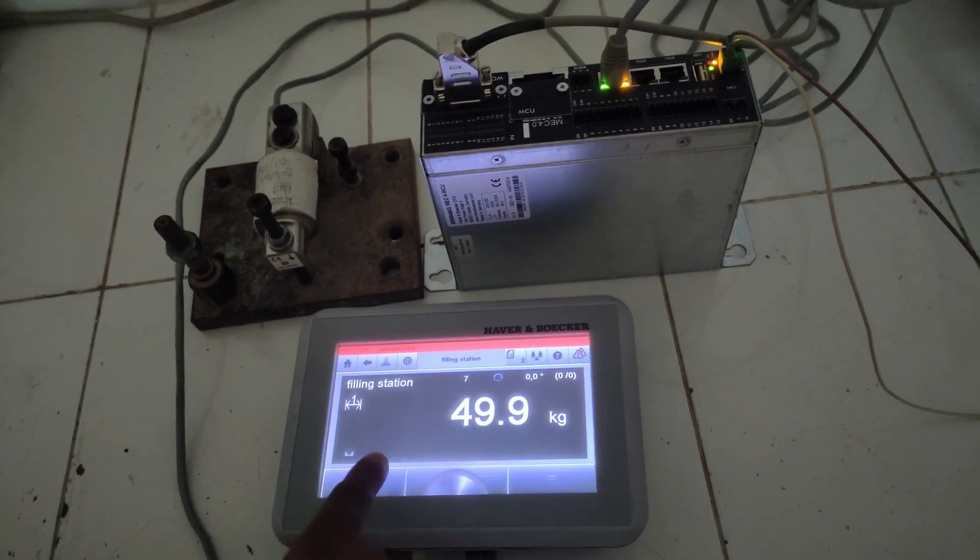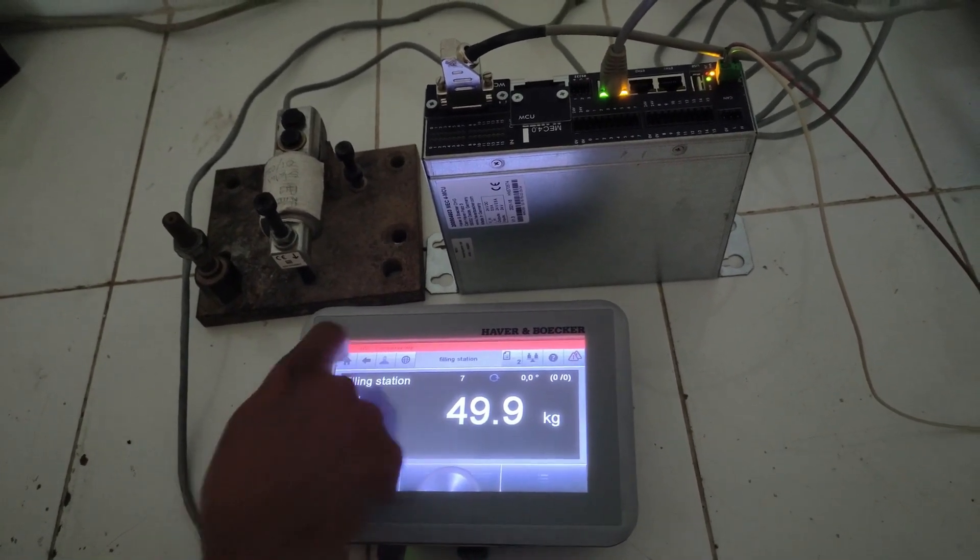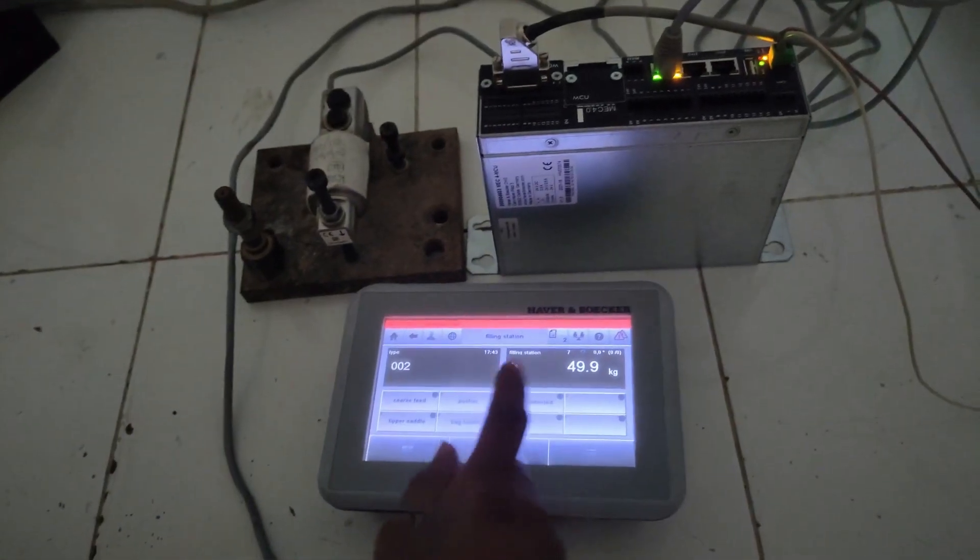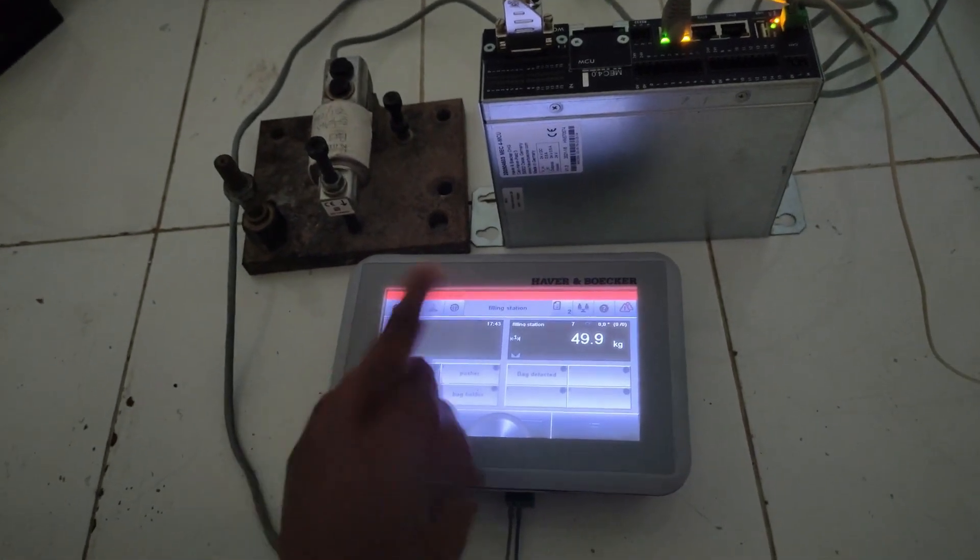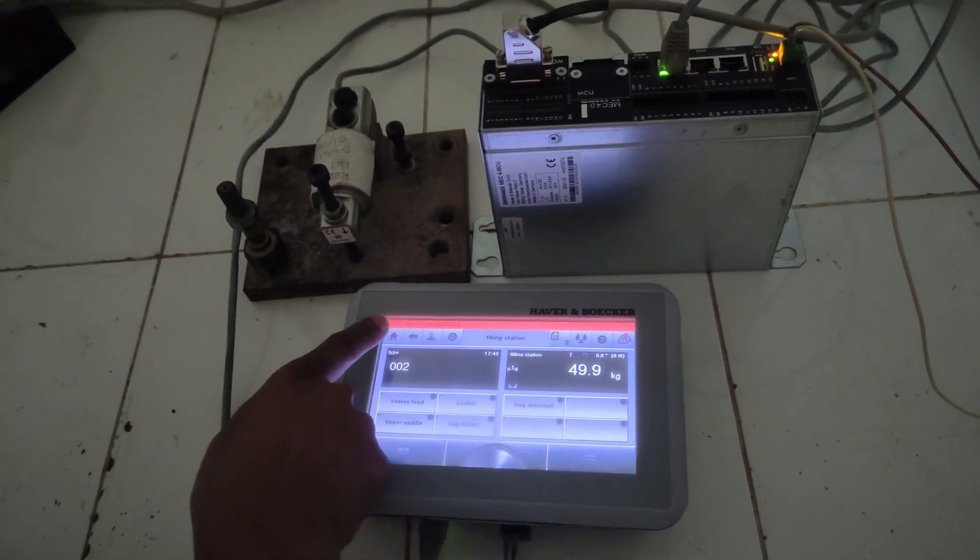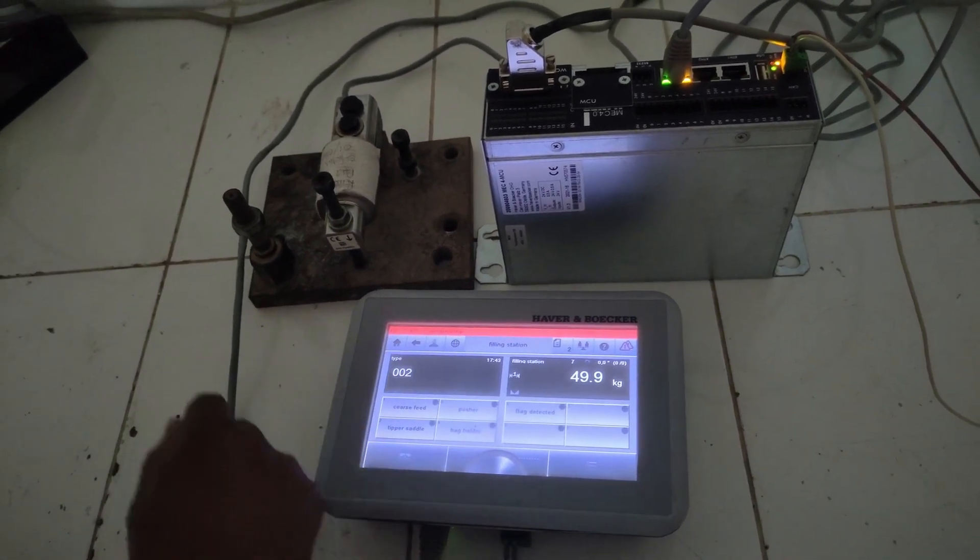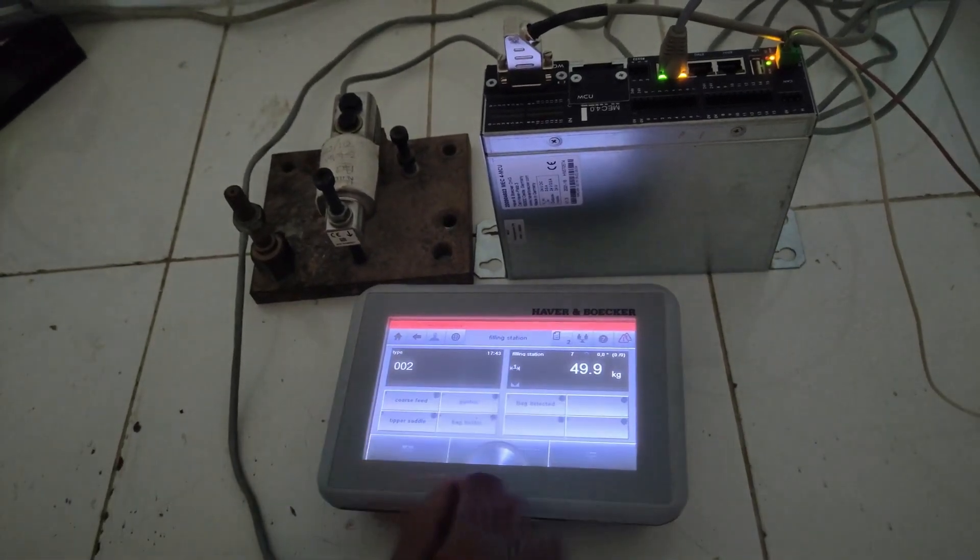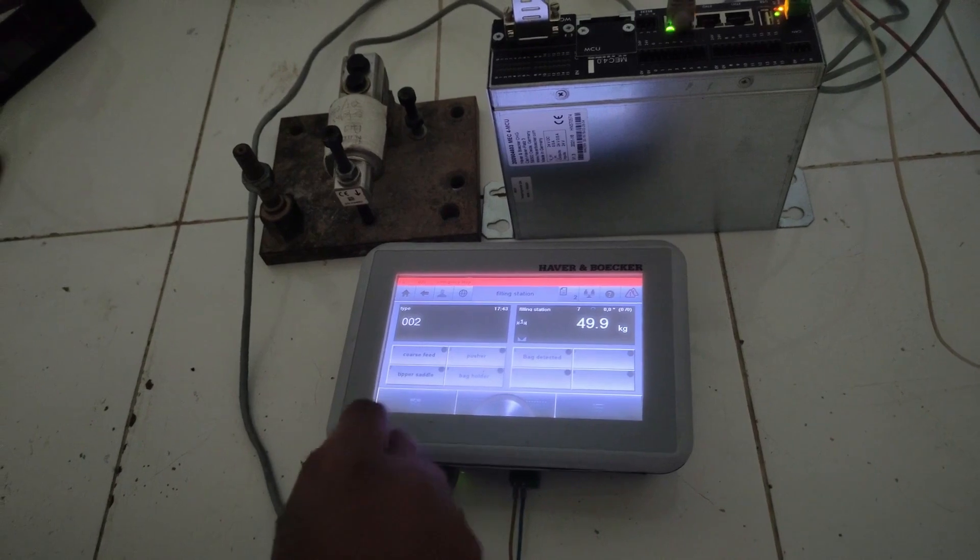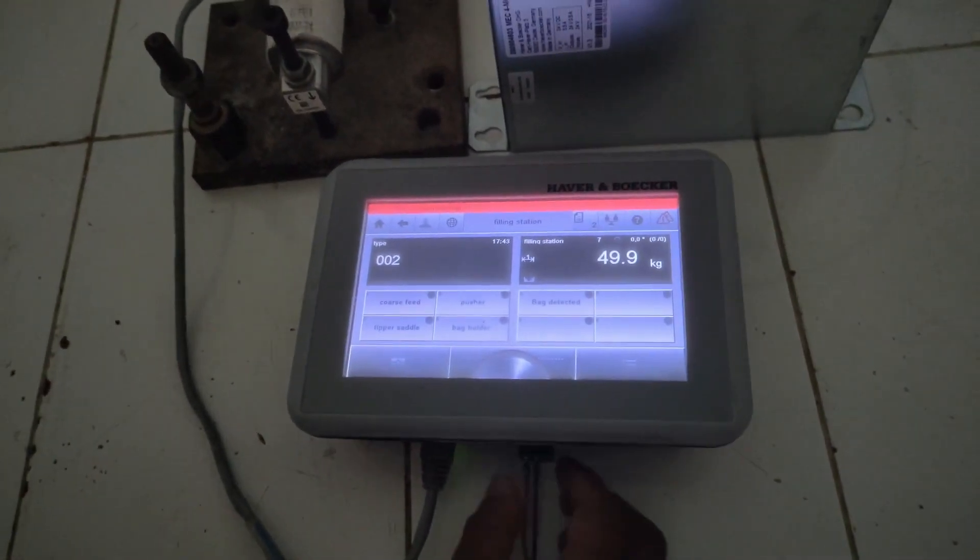A few days back we faced a problem where if you click one button, it will take the action of the nearest button. For example, if I click the home button, it will click the back button. Currently it is solved by calibrating the touchscreen, but I want to show how we have done it.